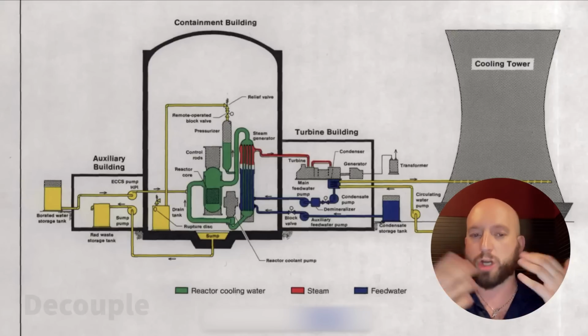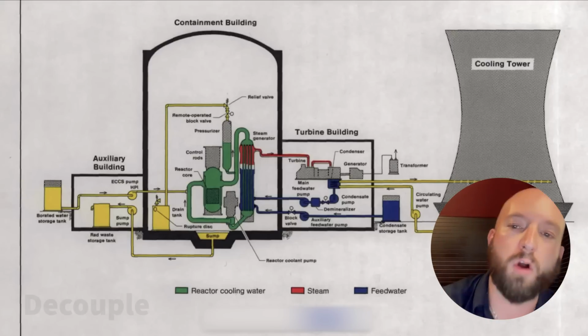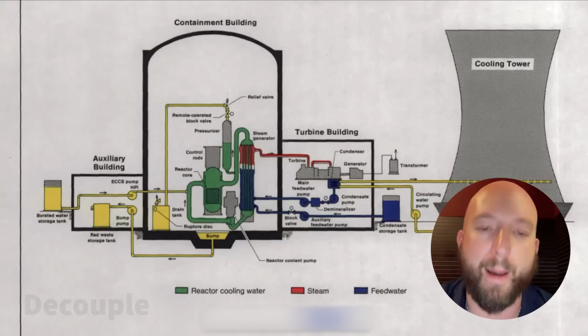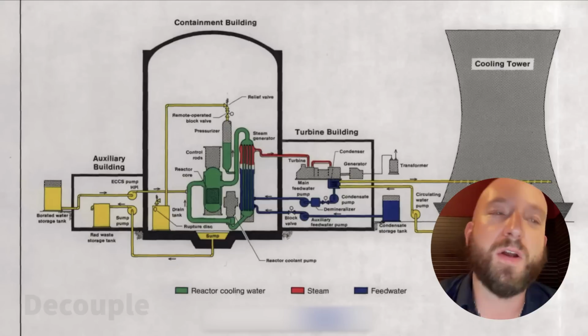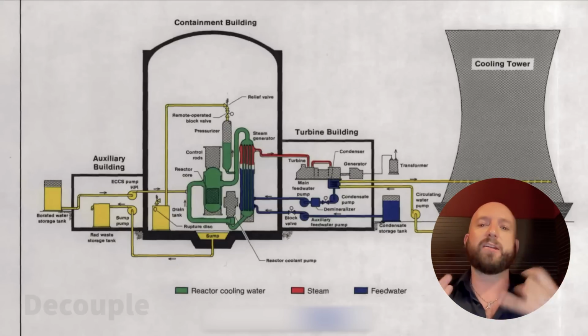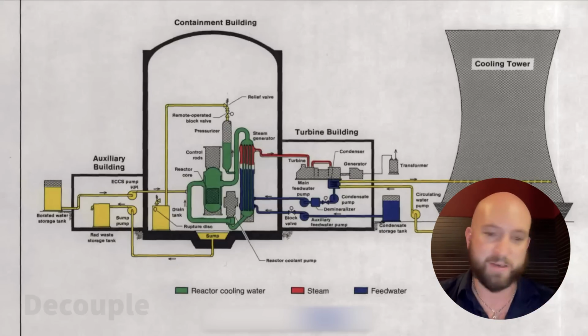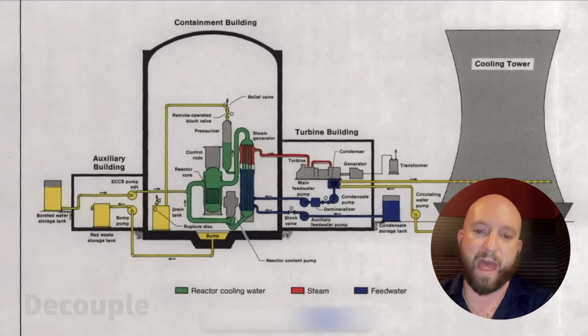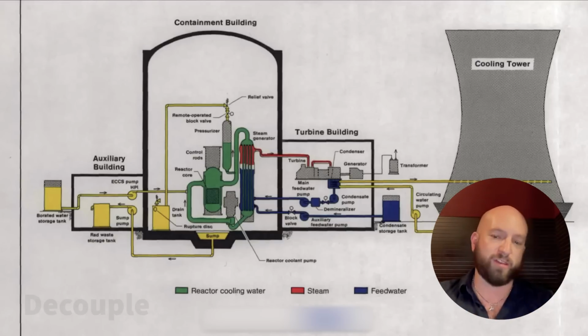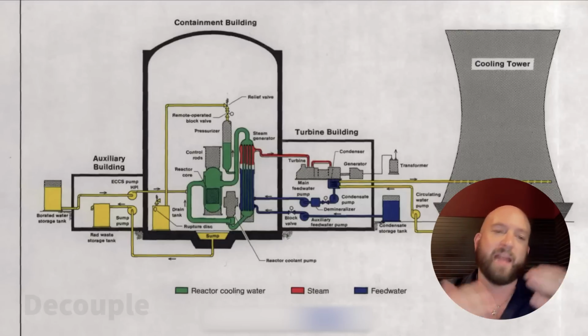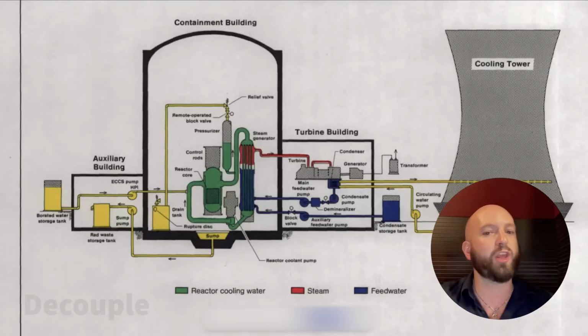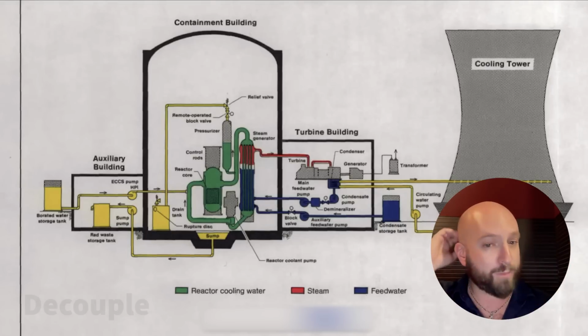Feed water transients, turbine trips, and so on are things that are called in nuclear engineering anticipated operational occurrences, or AOOs, which is a really complicated way of saying that these are things that we expect to happen during the plant life, and the plant should be really well designed to be able to deal with that situation. And so right now, although this is obviously an abnormal situation, it's not anything remarkable. Turbines trip, feed water pumps shut down. This is something that the system is designed to be able to do and not even be considered a major accident. So there's nothing here right now that's really that abnormal.